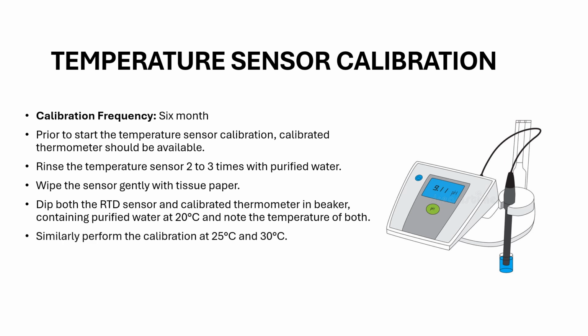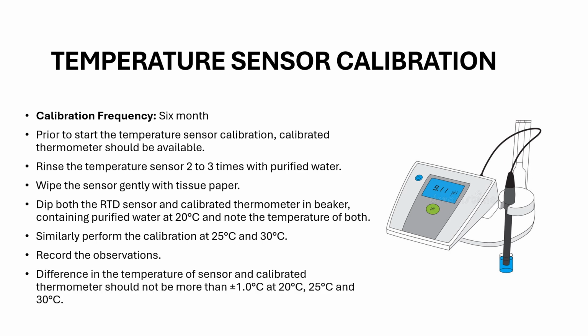Then repeat this process at 25 degrees C and again at 30 degrees C, and at each temperature allow the reading to stabilize. Then record the temperature from both devices, right? After recording the observation, verify that the temperature difference between the RTD sensor and calibrated thermometer is within plus or minus 1.0 degrees C for each reading at 20 degrees C, 25 degrees C and 30 degrees C. This small margin confirms the accuracy of the sensor, right? In this way you can calibrate your temperature sensor.